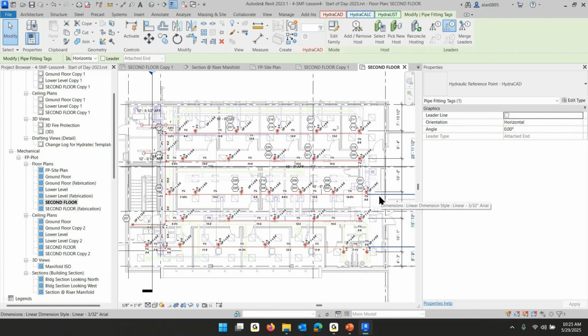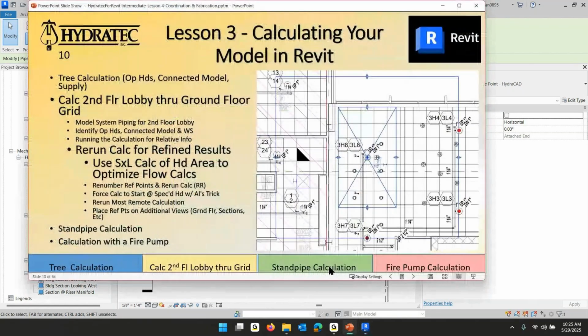Yes. So one of the things I'm going to go over is, yeah, I know that's hydraulically most remote, but everybody likes to see the calculation start at the furthest place on the furthest line. I want to force that to happen. Let me stick with the slides to get us there. But the first thing my slides say that I want to look at is, do I really need 196 square feet per sprinkler? If I can get away with it, why not?